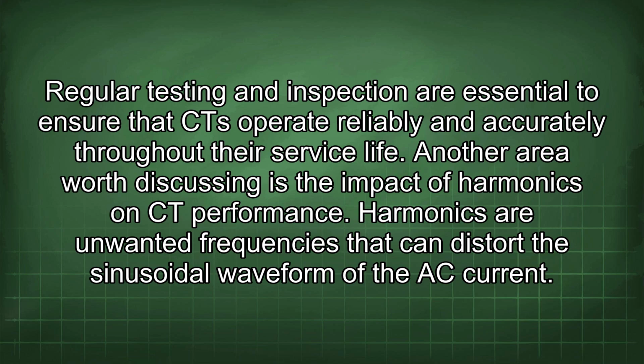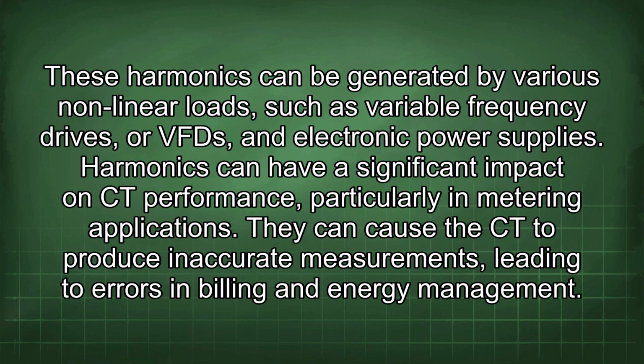Another area worth discussing is the impact of harmonics on CT performance. Harmonics are unwanted frequencies that can distort the sinusoidal waveform of the AC current. These harmonics can be generated by various nonlinear loads, such as variable frequency drives, or VFDs, and electronic power supplies. Harmonics can have a significant impact on CT performance, particularly in metering applications. They can cause the CT to produce inaccurate measurements, leading to errors in billing and energy management.